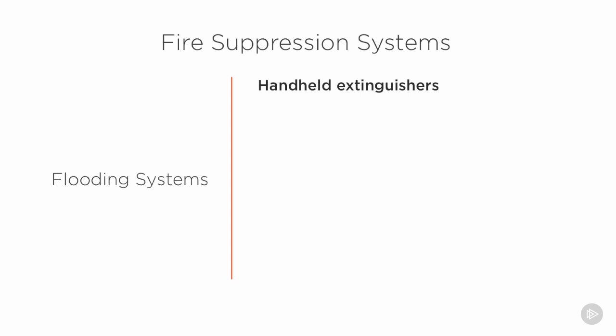Now, the one thing to remember, of course, when we're talking about handheld extinguishers is that the first priority in any situation is always life safety. And before trying to put out a fire with a handheld extinguisher, we should sound the alarm so that people have a chance to evacuate. Because if a person tries to put out a small fire with a handheld extinguisher, but they're not successful, it could be that people are not able to get out properly. So with a handheld extinguisher, in fact, many fire departments will tell you, don't try and put it out. Just call us. It's better for you to get out of the building so we can get in there to focus on the fire than it is for you to try and put it out and maybe make things worse.